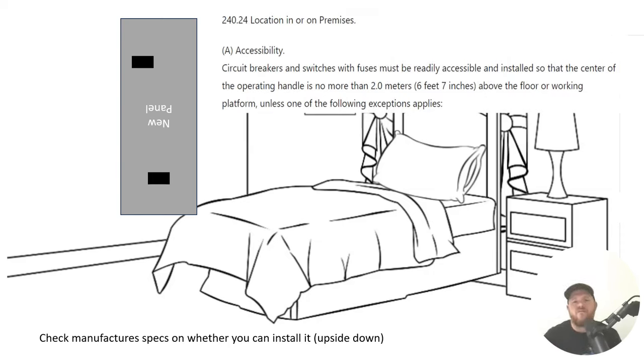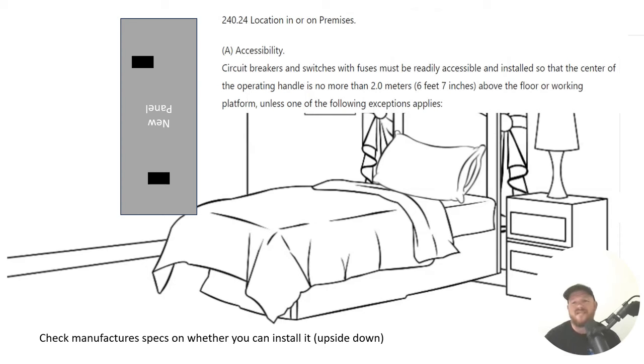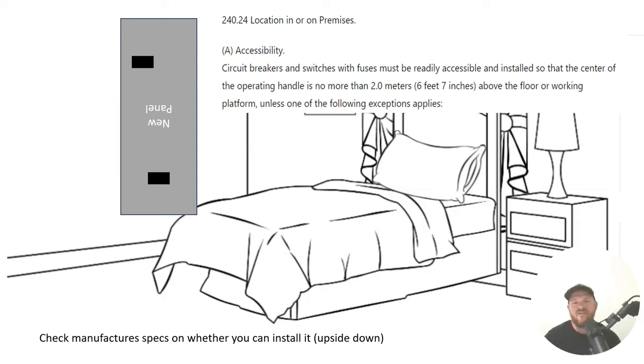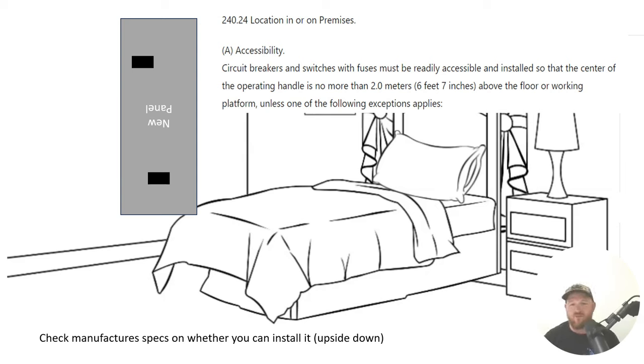Let's look at the paraphrase code language. It says circuit breakers and switches with fuses must be readily accessible and installed so that the center of the operating handle is no more than 6 foot 7 inches above the floor or working platform unless one of the following exceptions apply.